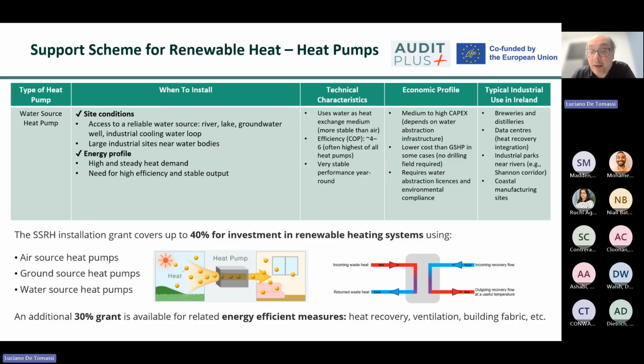Water source heat pumps utilize heat from surface water bodies or groundwater sources and can achieve very high efficiencies due to the stability of water temperatures throughout the year. They are especially suitable for large-scale installations, district heating systems, or industrial facilities located near rivers, lakes, or suitable aquifers.